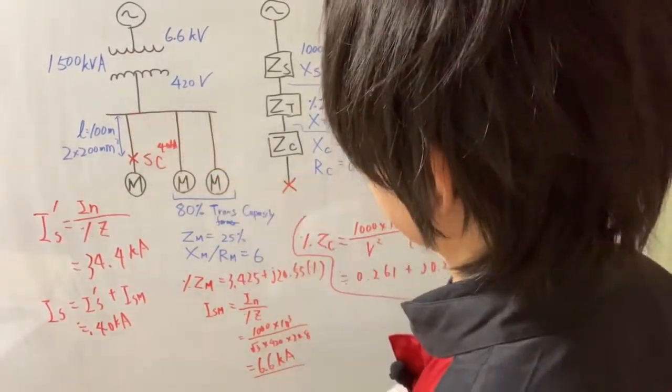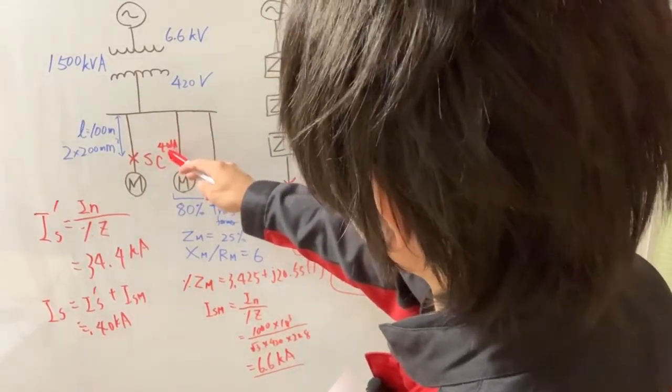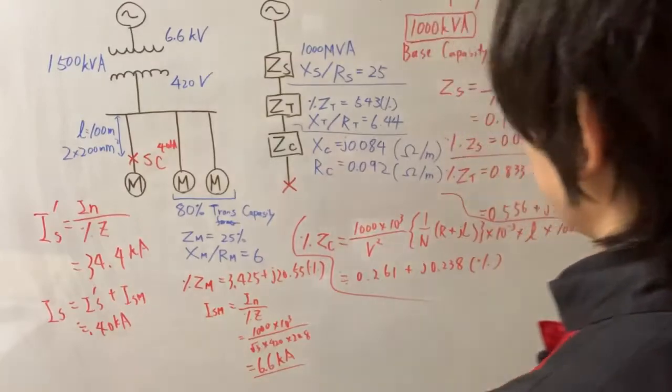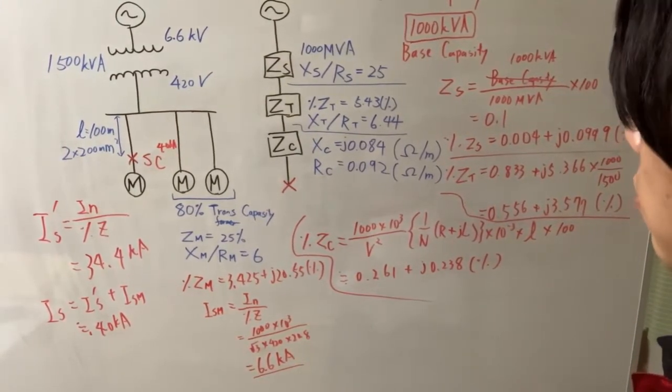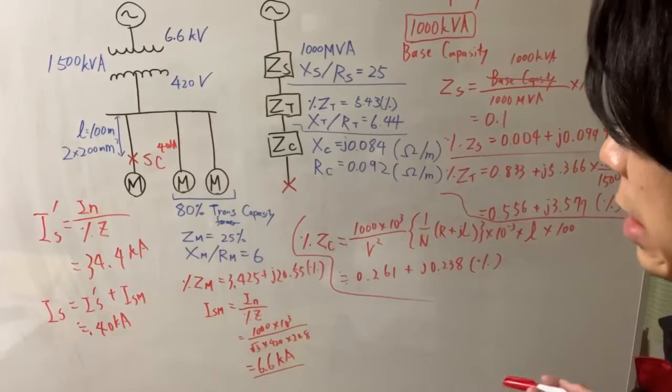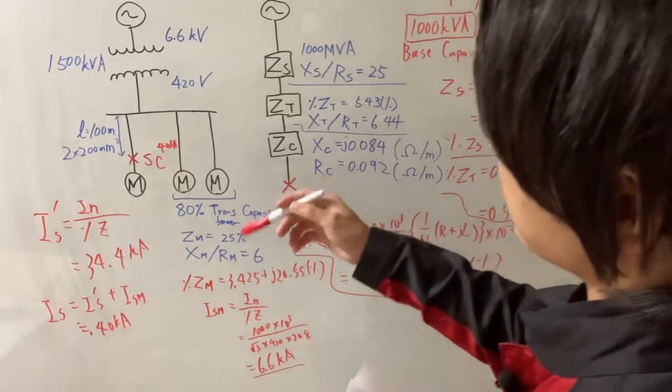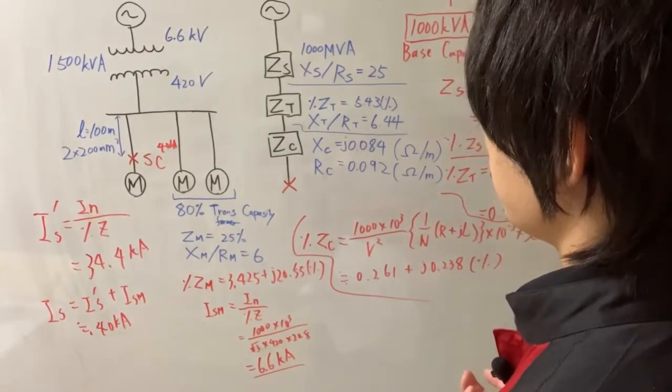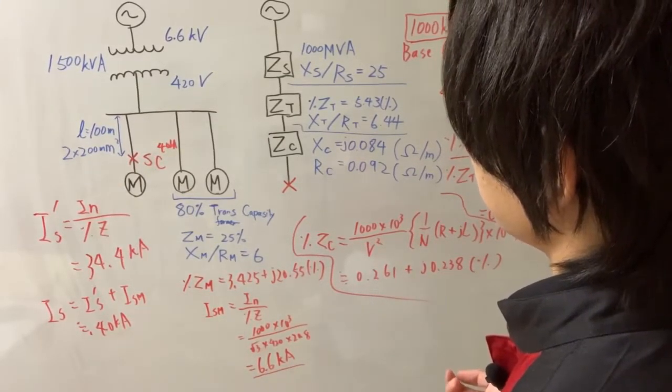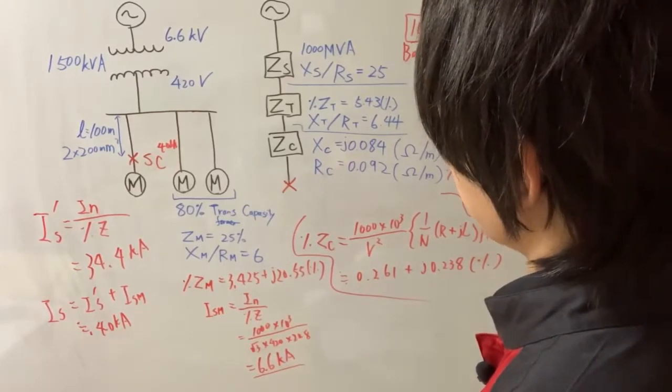So the available fault current is 40kA. So these devices like circuit breaker should be greater than 40kA SCCR. So like 45kA SCCR or 65kA or even 100kA, it's up to you. But generally, the higher SCCR tends to be more expensive and size also increases. So engineers have to make an optimal design for each device.